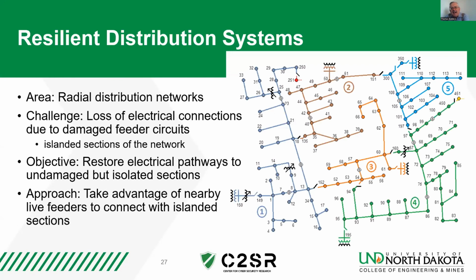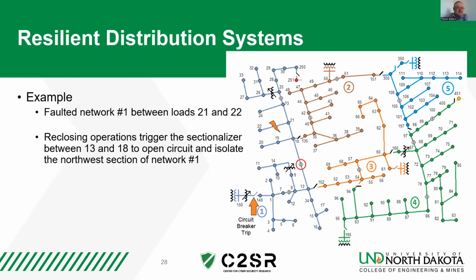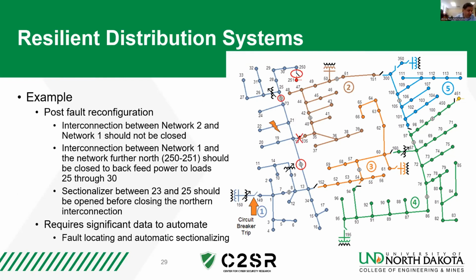So here we show a basic set of distribution networks, different neighborhoods, for example, being serviced by different substations. The different colors represent the different areas. If a fault takes place in one location, the circuit breaker for that substation will usually open, and reclosing operations will take place, and a sectionalizer will try to minimize that portion of the distribution network that is faulted. And so we can begin to manually backfeed to provide power to certain sections that were not damaged by the fault. Trying to do this automatically is the goal, and so we can then begin to close these tie switches between the distribution areas more completely.